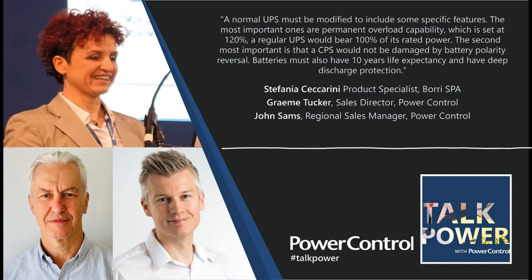Yes, definitely. As John mentioned earlier, as long as while on battery, with no mains available, the load is not regenerating, then it's totally fine to back it up with a UPS or a CPS. No problem. Very good. That's good to know.